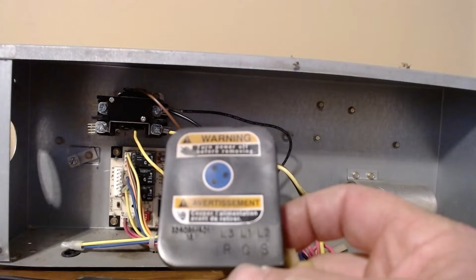And then here's your compressor plug that goes on the compressor. You can see right here on the plug, it says L1 is common, L2 is start, and L3 is run. If you ever get one where this has been blown off the compressor and you pull it and look and there's a little metal probe sticking inside of there, you have a problem. If you ever open it up and you see all that is dry rotted and cracked, it very well may be getting cross voltage between one of the other terminals because of that as well.